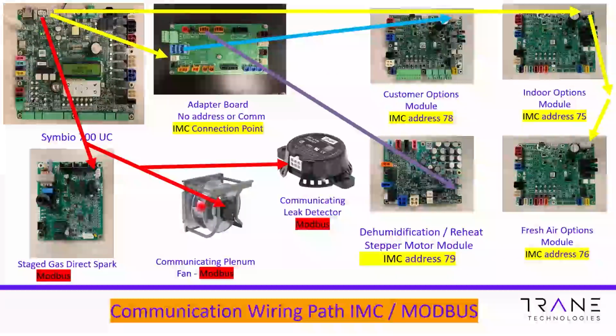Modbus and IMC. IMC is your inter-module communication connection, so it's going to be talking in between boards. And your Modbus is talking to all the fans and the controller. So we do have two different communication lines in here. This shows you Modbus goes to our staged ignition control board, our plenum fan, and the communicating leak detector. IMC talks to all the modules.